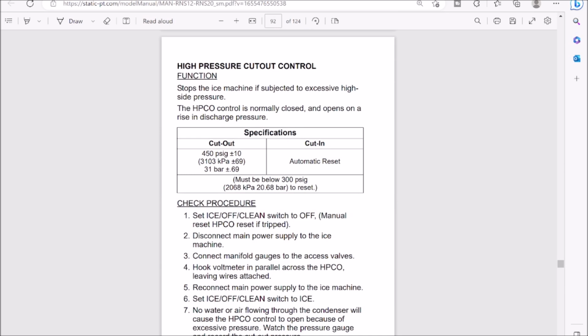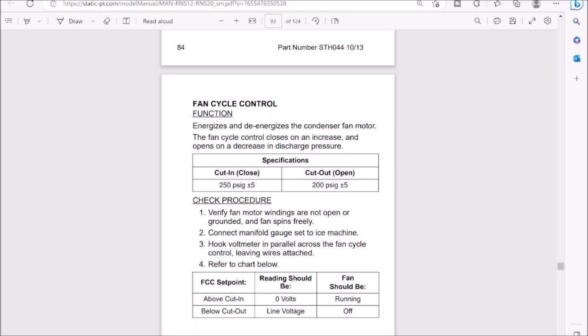So let's go back to our service manual here. High pressure cutout control. It stops the ice machine if we have high head pressure. So that means if we're getting up to 450 psi, it's going to shut off. And then once we get back below 300 psi, it's going to close that switch again. Now we could have a high pressure situation if this fan's not running. So how this fan runs is we have a fan cycle control.